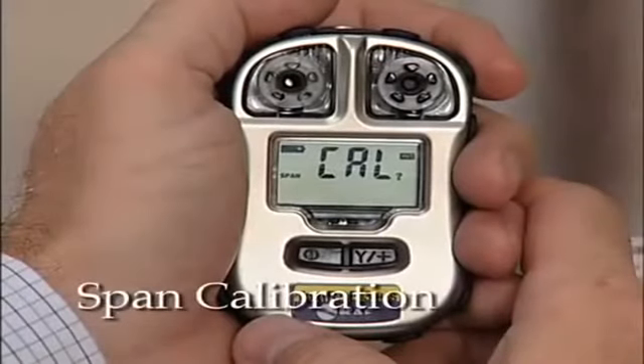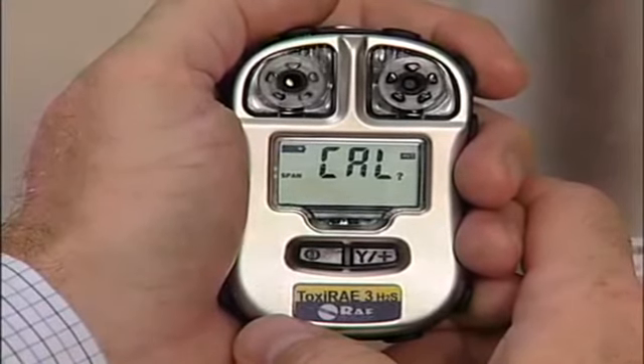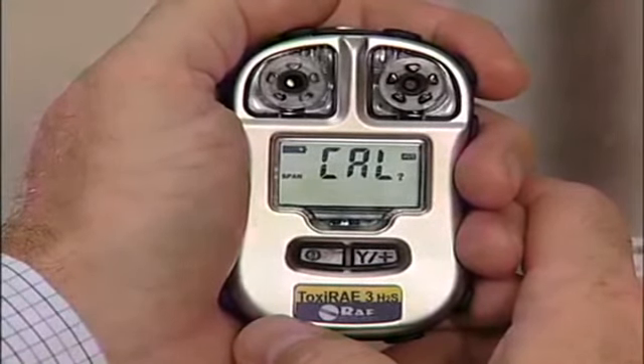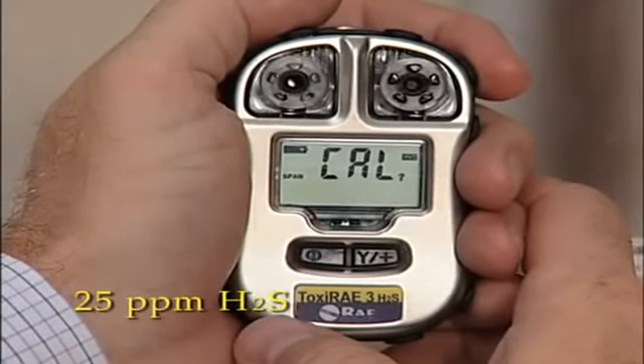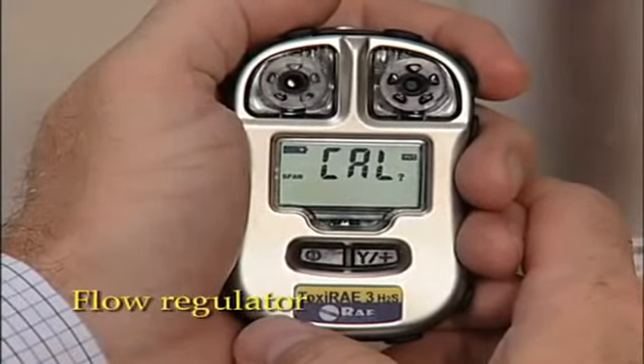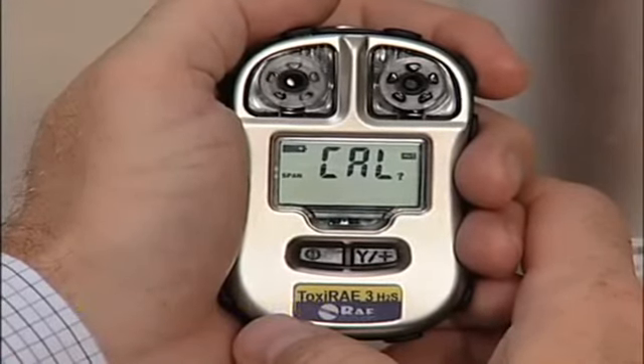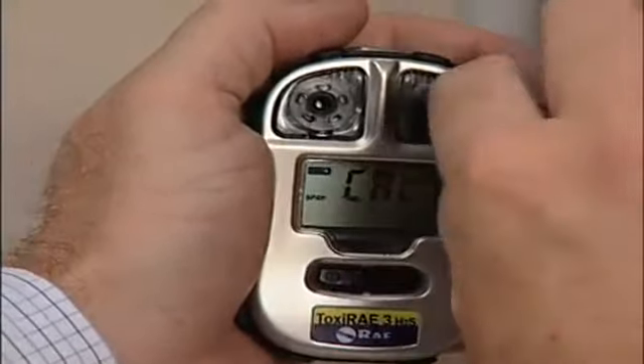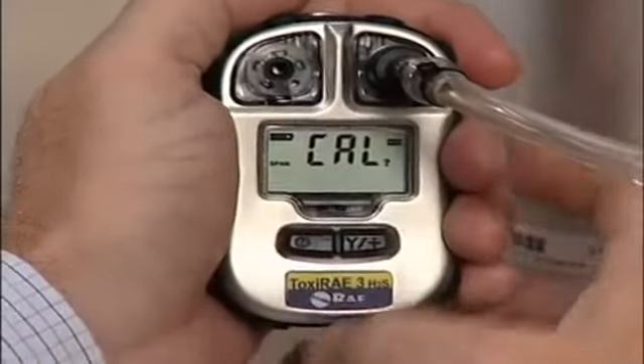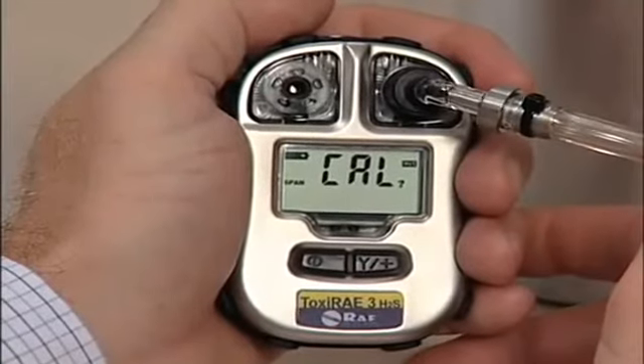Now for the second part: the span calibration. This procedure determines the second point of the sensor calibration curve for the ToxiRAE 3 sensor. Performing a span calibration requires using the calibration adapter, a flow regulator, and a tank of span gas. Attach the calibration adapter over the inlet port on the front of the ToxiRAE 3 by pressing it in place.